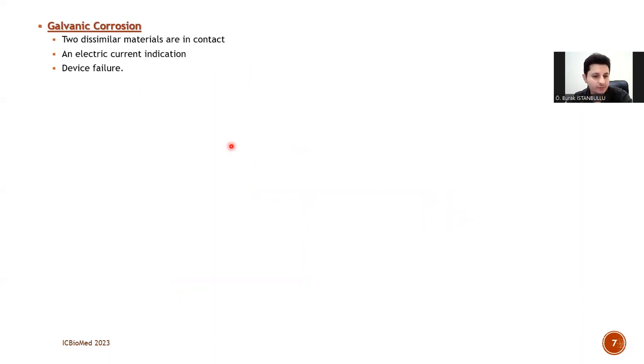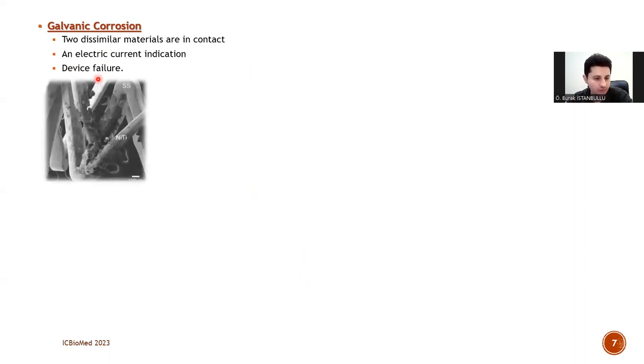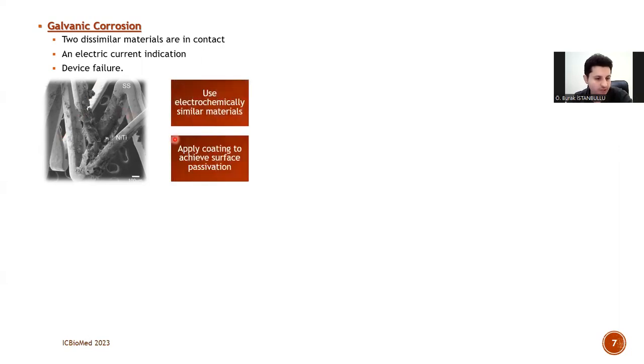One of the most common biomaterial corrosion mechanisms in the human body is galvanic corrosion. Galvanic corrosion occurs when two dissimilar materials are in contact with each other. In this case, while one of the materials acts like an anode, the other presents a cathodic feature. This may lead to material and device failure due to corrosion, as shown in this picture. Using electrochemically similar materials or applying surface coating can inhibit or completely block this corrosion process.